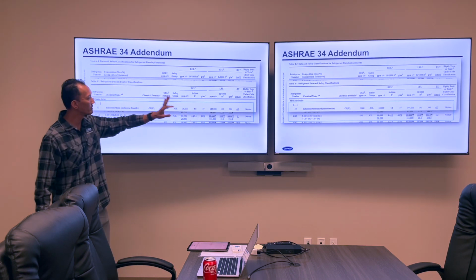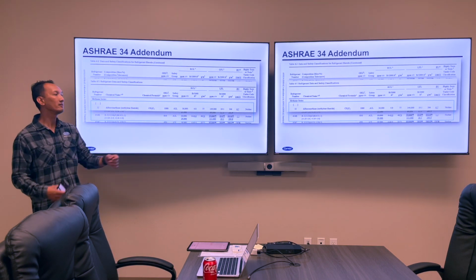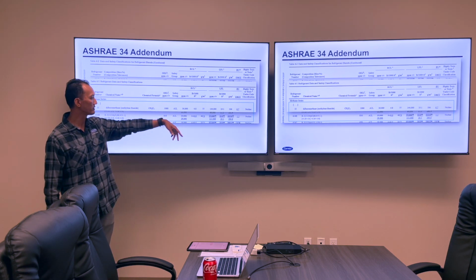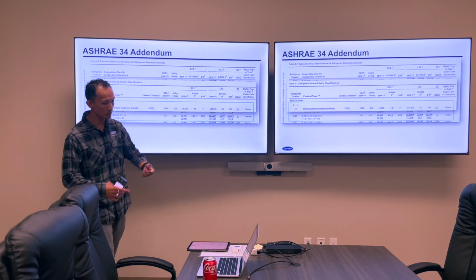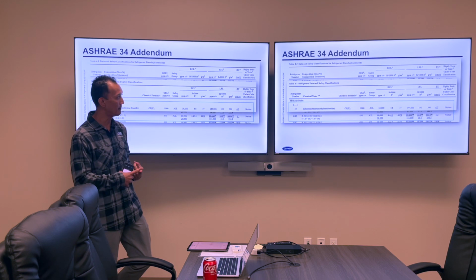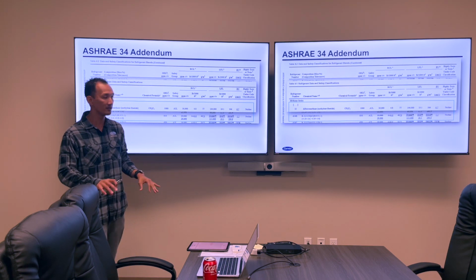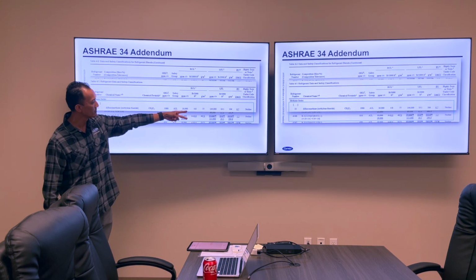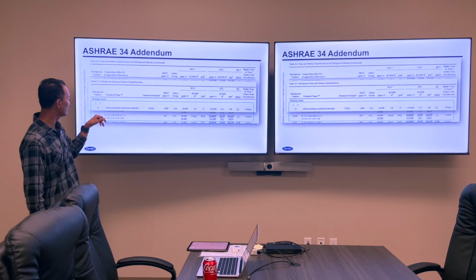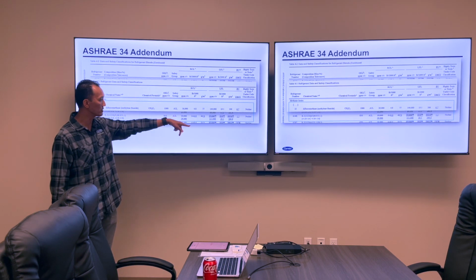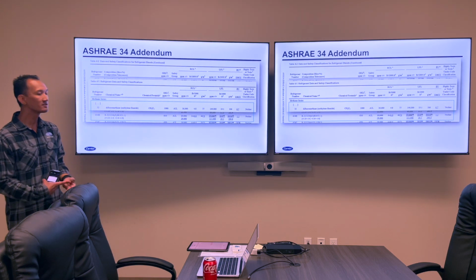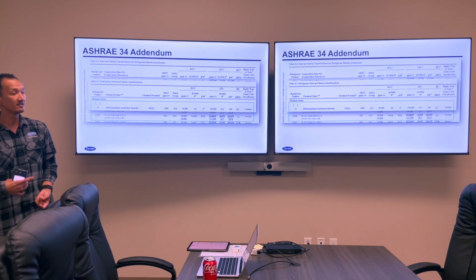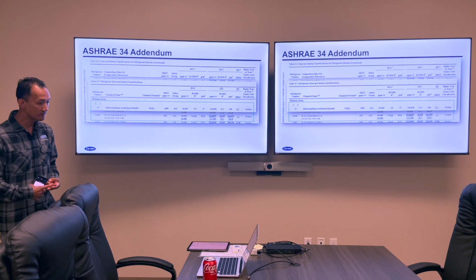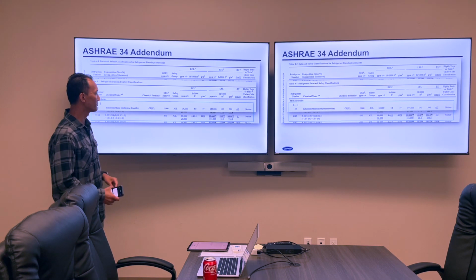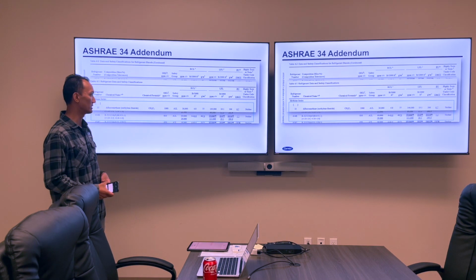If you remember, for R410A, it was 26 pounds per 1,000 cubic feet, since we had to worry about it displacing oxygen in a space. Now they are slightly flammable, so those two numbers for R32 and R454B are a lot lower compared to R410A. Something we have to think about when designing VRF systems for projects is that these numbers are a lot lower.